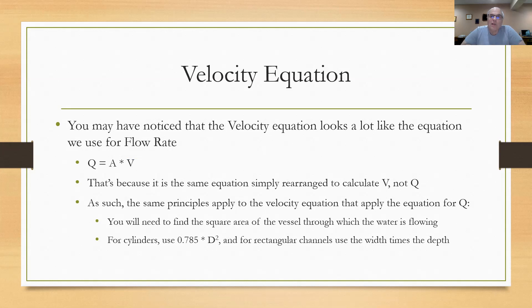When we do velocity equations, the principles that apply for flow rates also apply for velocity. You'll need to find the square area of the vessel through which the water is flowing. For cylinders, you can use 0.785 times the diameter squared, or pi 3.14 times the radius squared. For rectangular channels, we would multiply the width times the depth. You're getting a square area, just a plane in two dimensions.